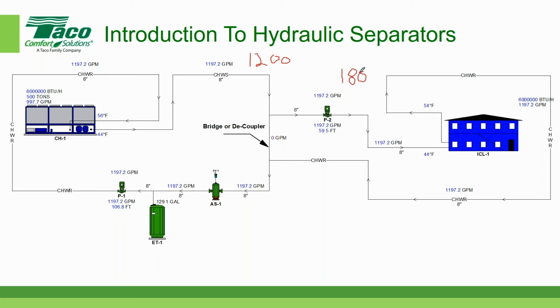How could that be? Well, we go back to our bridge. Again, this 1,200 rounds the corner, but we're going to draw off 1,800. Well, how can we draw off 1,800 if we only have 1,200 available? We're going to cross out these values here for a moment. Our new value is 1,800. That means across this bridge, in the opposite direction, we're going to have the difference between these two, in our case 600 gallons per minute. So again, 1,800 comes back on the return side over here, but 600 runs in the opposite direction, and therefore 1,800 minus 600 is 1,200, so that's how we get 1,200 back to our primary loop.